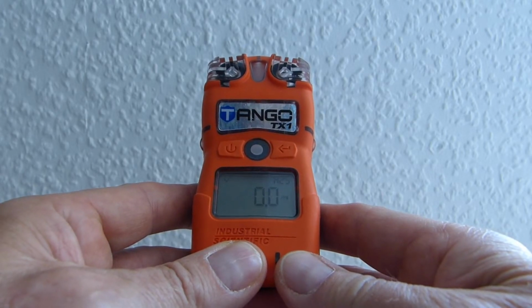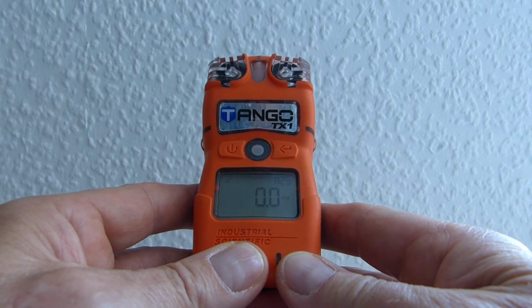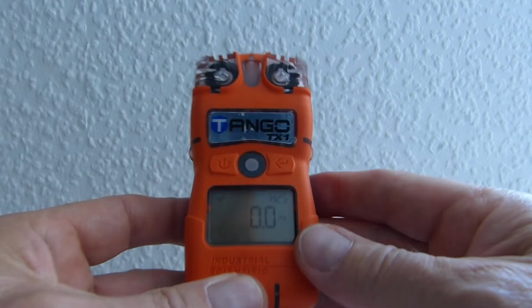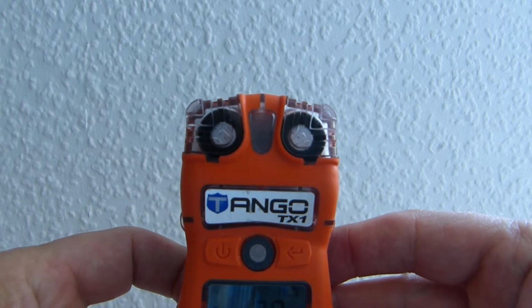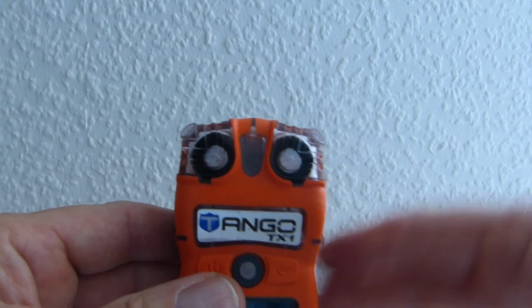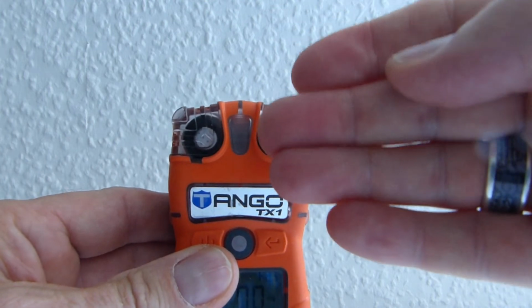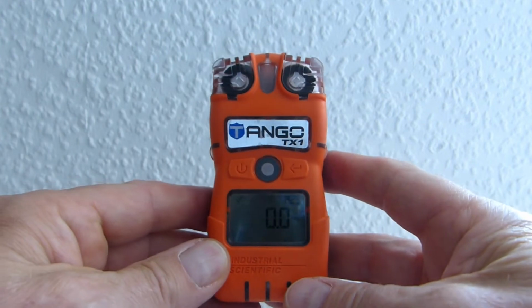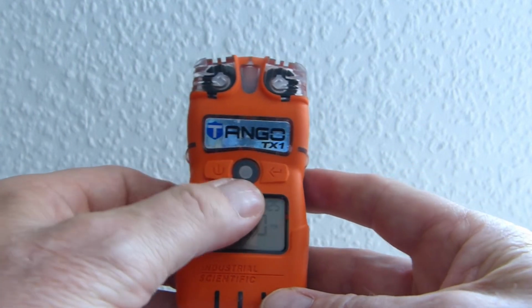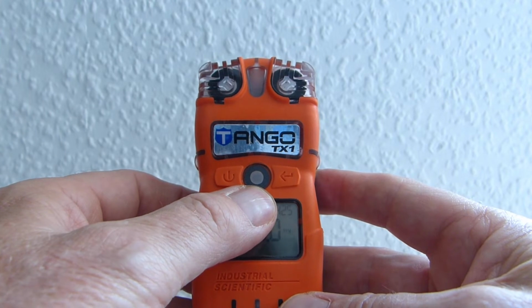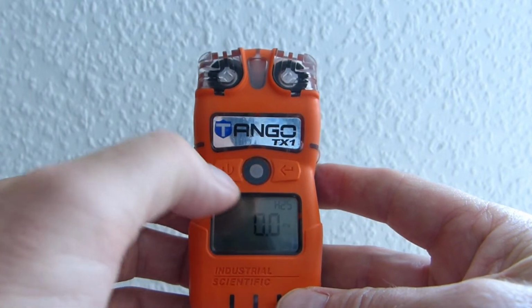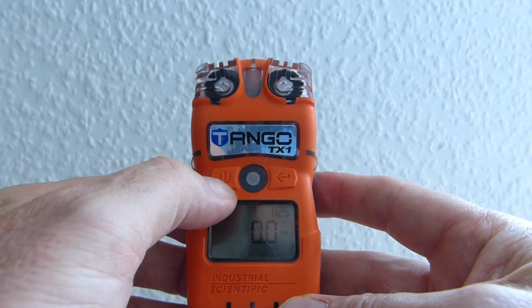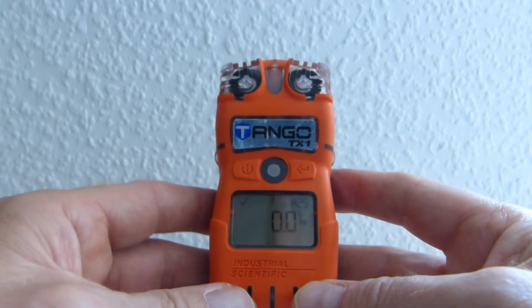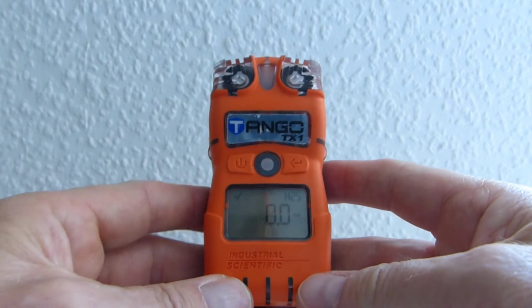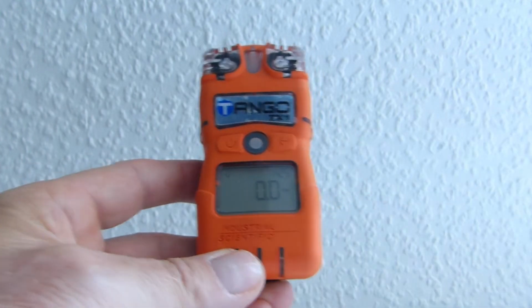I would like to make you familiar with the features of the Tango TX1. On top, you can see the two sensors detecting H2S. You have three sides to detect the gas from the front, from the side, from the top, on both sides of the instrument. In the middle, there is the speaker, which gives you the audible alarm from the instrument. The left button is the button to switch on the instrument, and the right button is the select button to select an option or a function that you want to use.